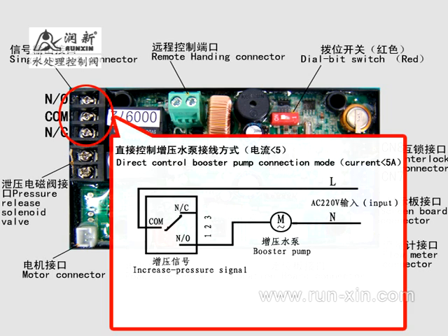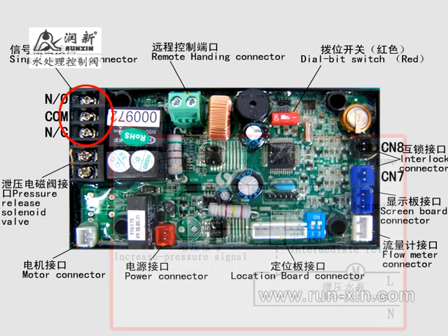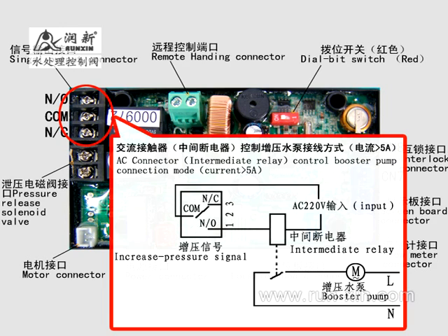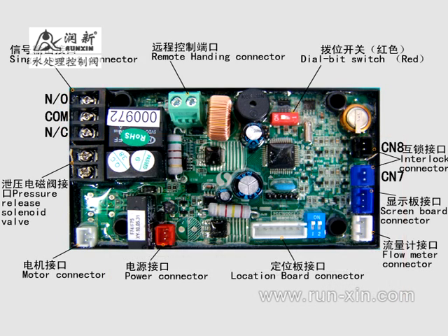When installing the system, because pressure from raw water is too low, or to ensure no hard water flows out from the outlet, you could install a booster pump in the water inlet or a solenoid valve in the water outlet. Use the 3 signal output connectors on the main control board: normal open, common, normal close signal output.